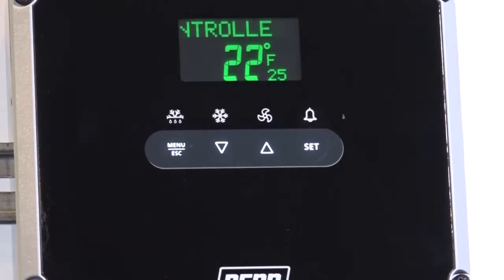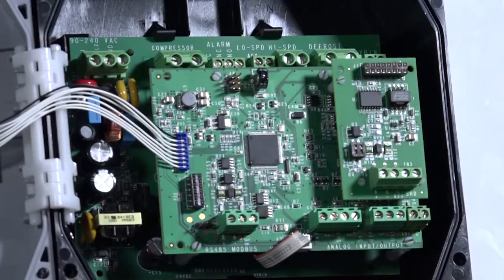The A525 controller uses 5 relays to control all aspects of a single condenser evaporator refrigeration system, such as a walk-in cooler or freezer. The first relay is used to control the compressor or liquid line solenoid. The relay can handle a 1 horsepower motor at 120 volts. The second relay is used to control the defrost cycle. It can be used for either electric strip heaters or a hot gas defrost cycle.